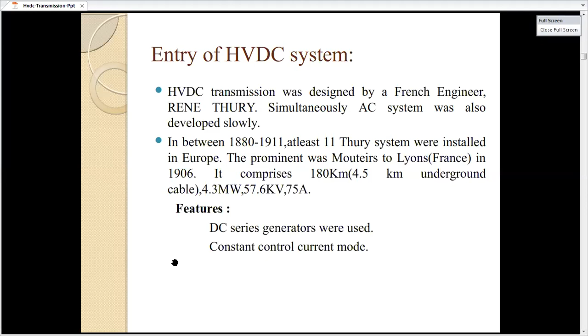Between 1880 and 1911, eleven Thury systems were installed in Europe. The prominent one was Moutiers–Lyon in France, in 1906. It comprised 180 kilometers, of which 4.5 kilometers was underground cable, with 4.3 megawatt, 57.6 kilovolt, and 75 ampere. What are the features? Some features of this HVDC system: DC series generators were used, and a constant current control mode was there.